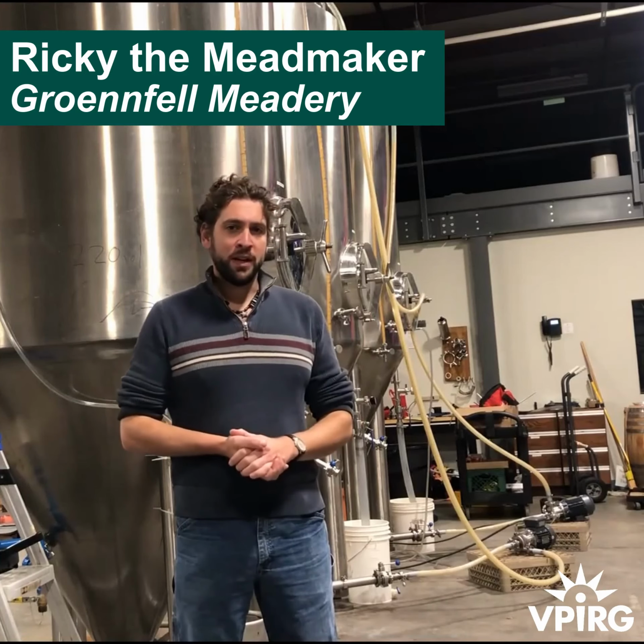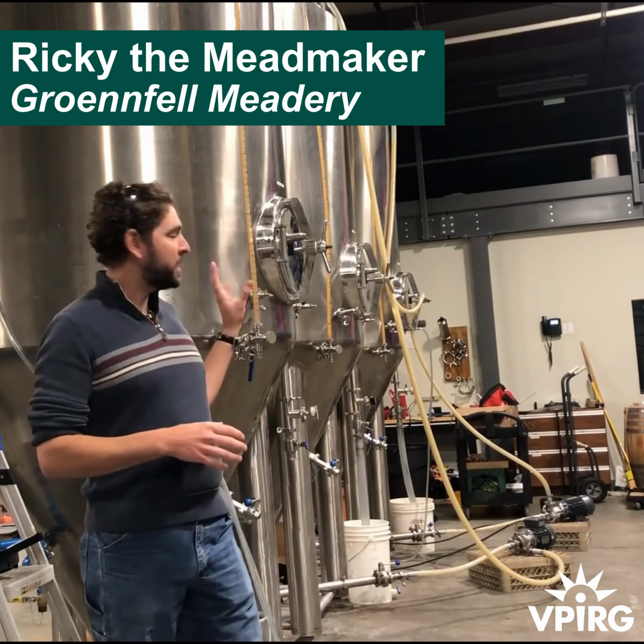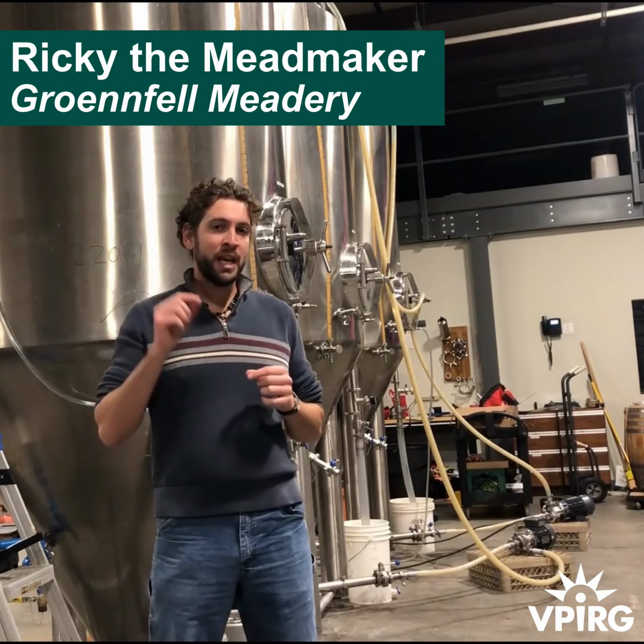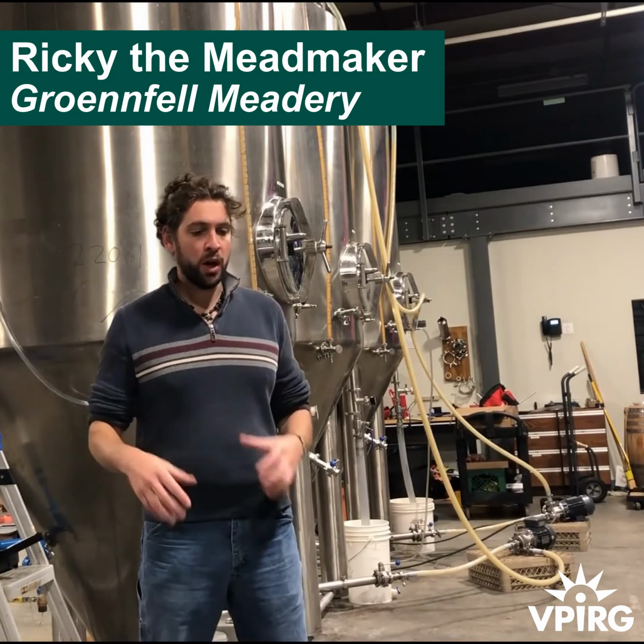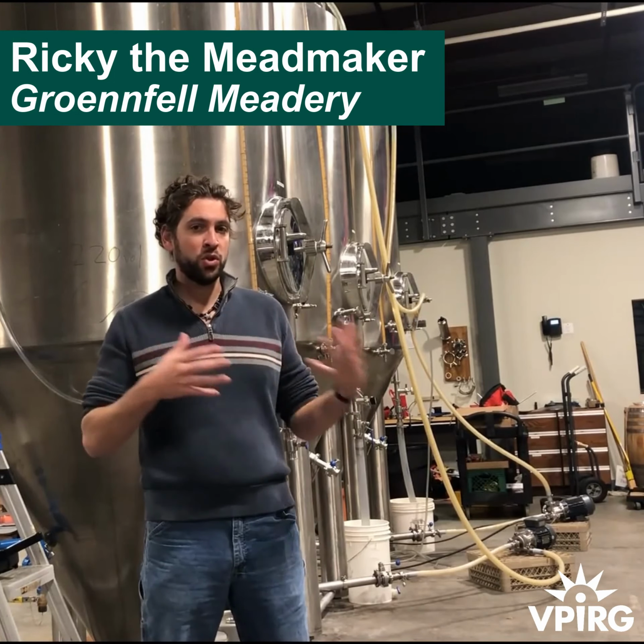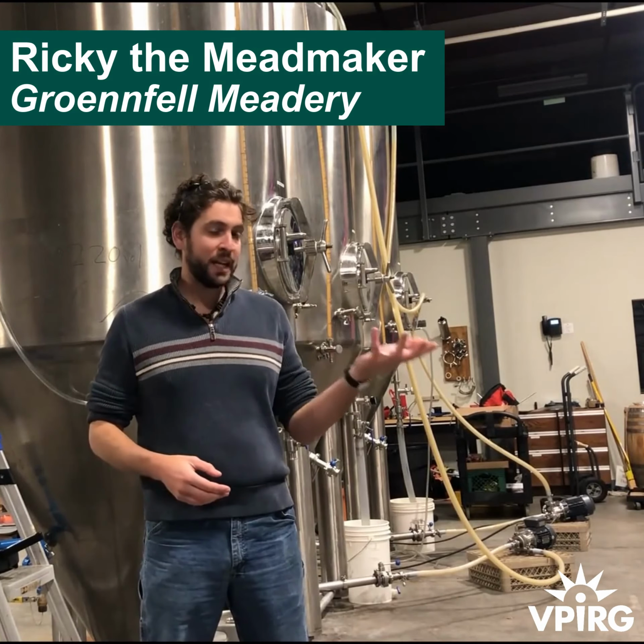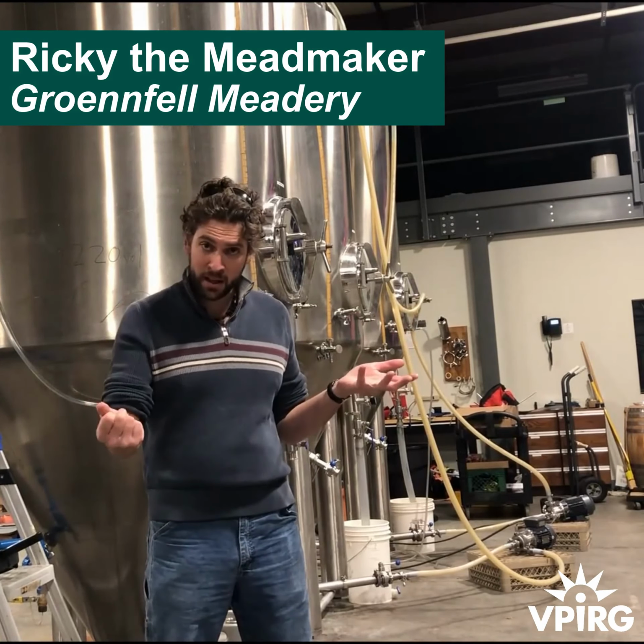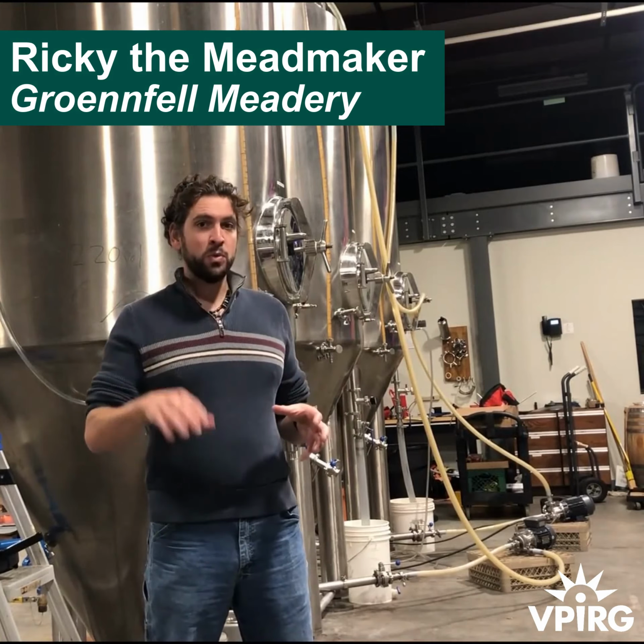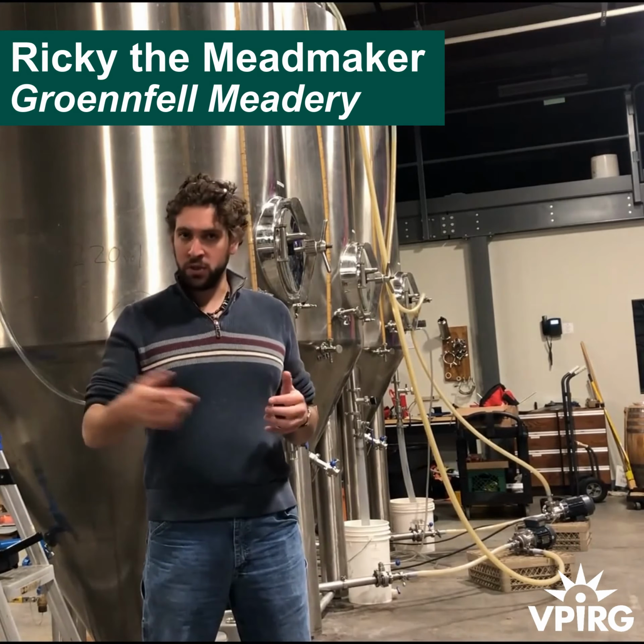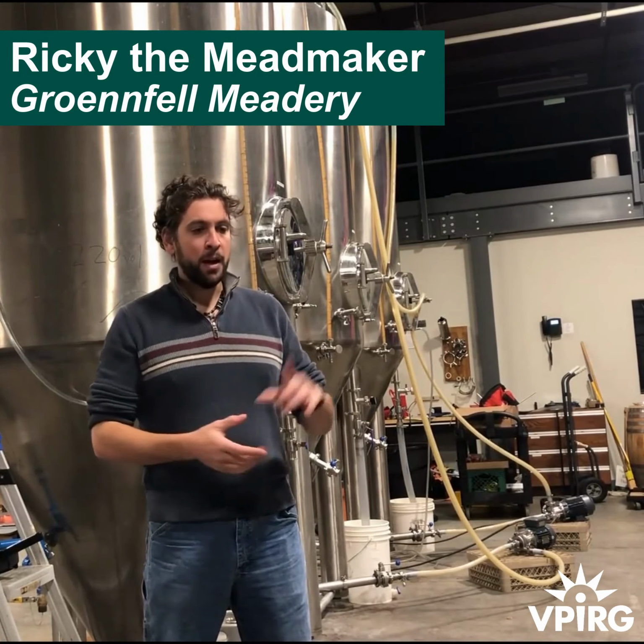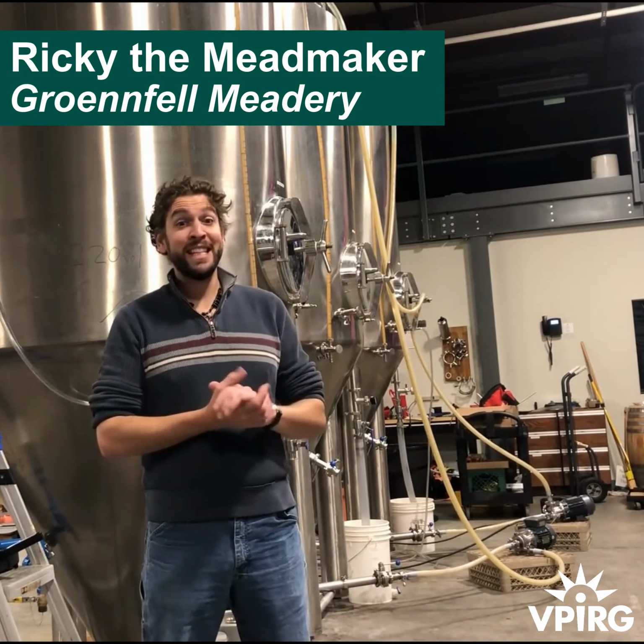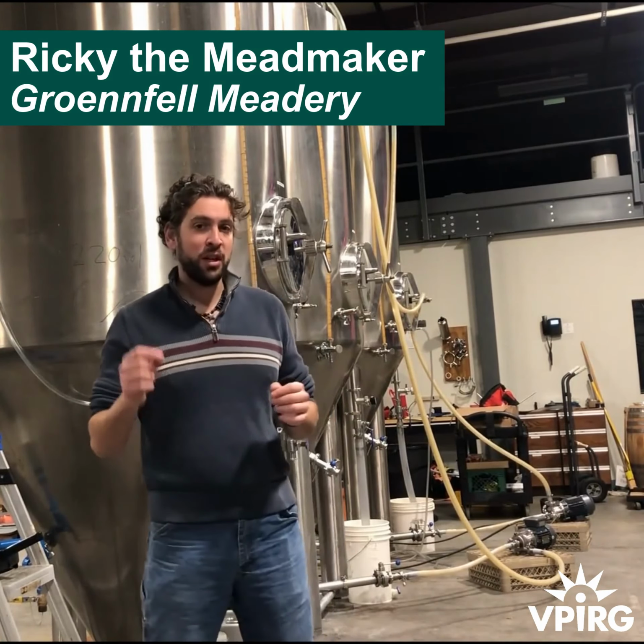One of the cool things we've done here at Groennfell Meadery is all of our tanks are programmed to tell our chiller when to turn on. A lot of breweries run their chiller 24/7 so that when their tank needs a cooling load, it's on immediately. What we did instead was keep a maintenance loop going, so the coolant is always moving, but the tanks might go 3, 4, 5, 6 days without needing chilling capacity.